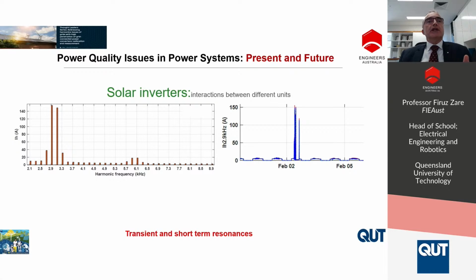So that's a short-term resonance or harmonic issue that can trip the network or can affect the transformer, the cable, or many other devices in the network. If you look at the current waveform for that specific frequency, around 3 kilohertz, the amplitude is significant, over 140 amps, and that is something happening in the short term.